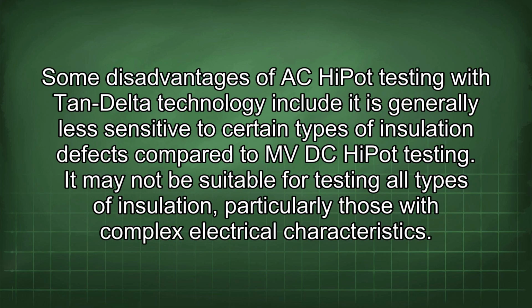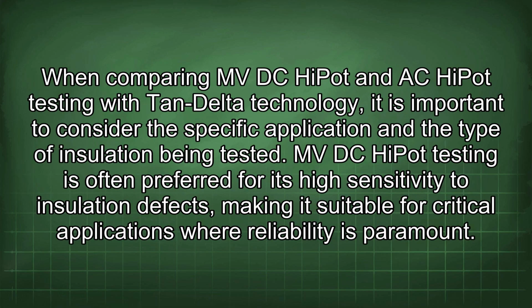Some disadvantages of AC HiPot testing with tan delta technology include it is generally less sensitive to certain types of insulation defects compared to MVDC HiPot testing. It may not be suitable for testing all types of insulation, particularly those with complex electrical characteristics. When comparing MVDC HiPot and AC HiPot testing with tan delta technology, it is important to consider the specific application and the type of insulation being tested.